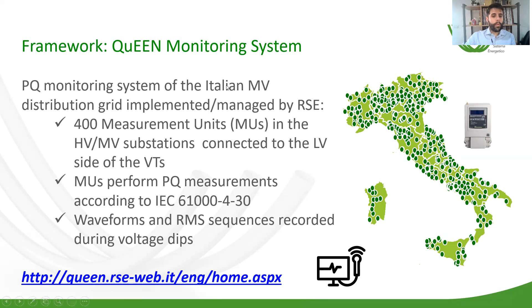In the Italian distribution grid, we have a certain number of isolated neutral systems. In this kind of topology, it is well known that faults involving ground produce a sinusoidal zero sequence that can cause voltage transformer core saturation, resulting in false voltage dips. As we can see from the picture in the slide, we have a reduction of the voltage at the output of the transformer, characterized by a distorted waveform. And this reduction is not a reduction of the voltage supply, but only the result of the saturation of the voltage transformer. If you want to consider voltage dips as a parameter to evaluate the power quality of our network, these events have to be removed from statistics.